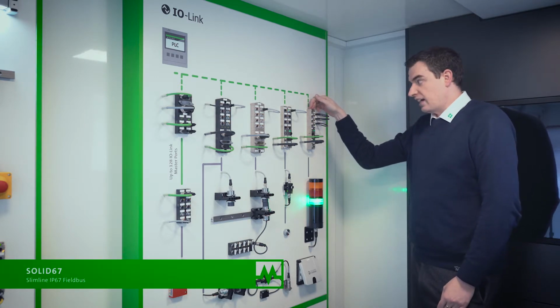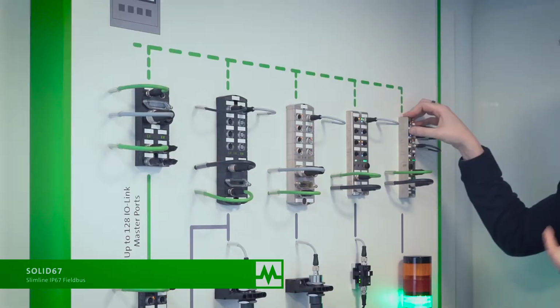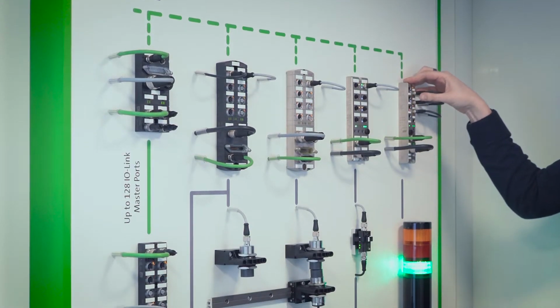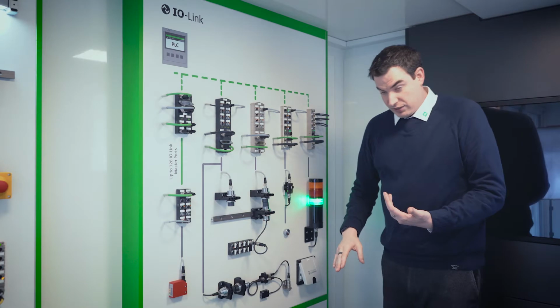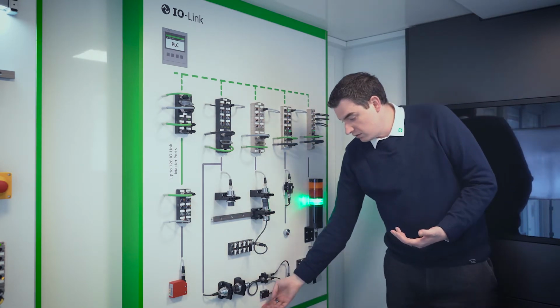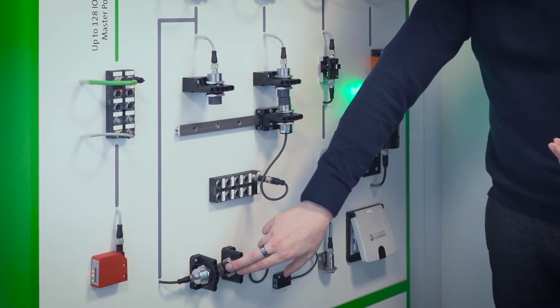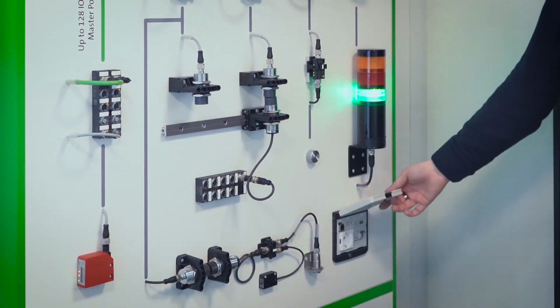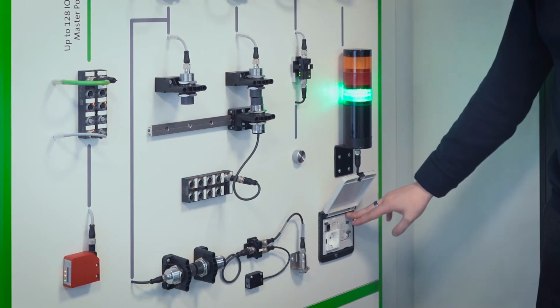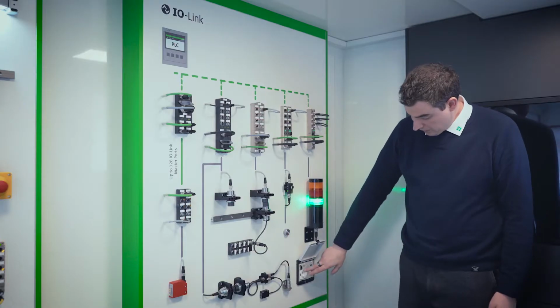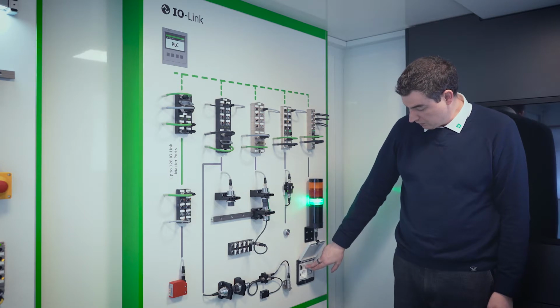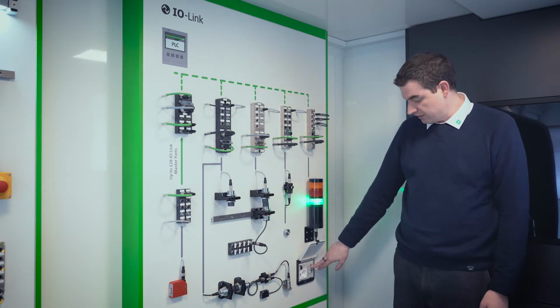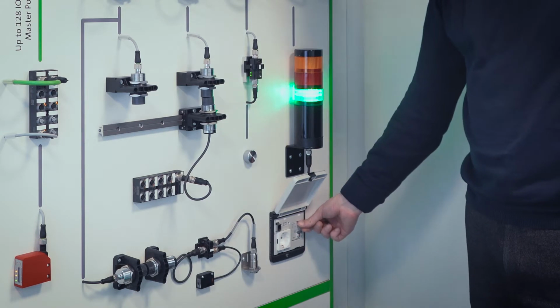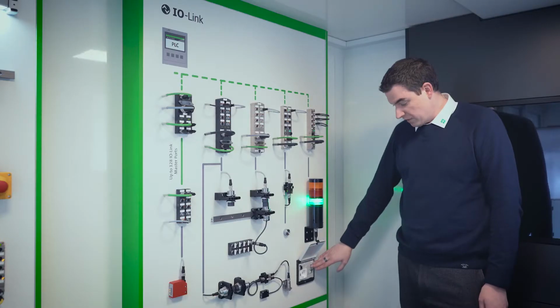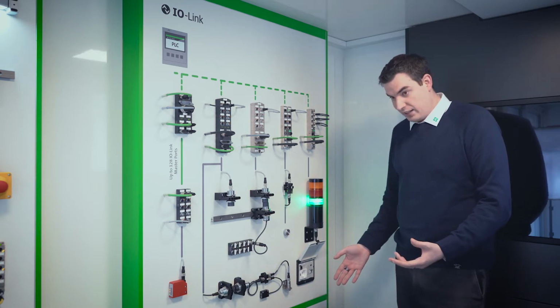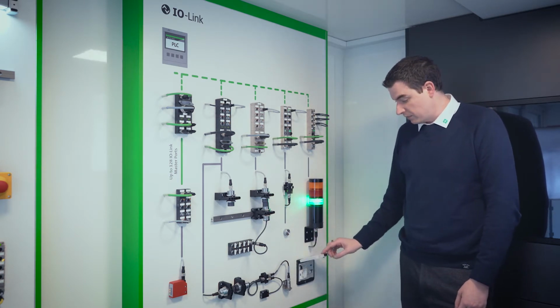With the 30mm, this is ideal for attaching to aluminium extrusion profile or onto a robot head because it's smaller and more lightweight. The inductive couplers can also be used for standard sensors, and that's the maximum air gap set there. We do have a front panel interface. It's not particularly to do with IO Link, but it's on the same board, where we have a power socket, RJ45, USB communication, and a placement to be able to fit your own RCBO within. Now that's not sold by Murrelektronik, that is completely down to yourselves to buy, and it's completely universal so that you can buy that from anybody.